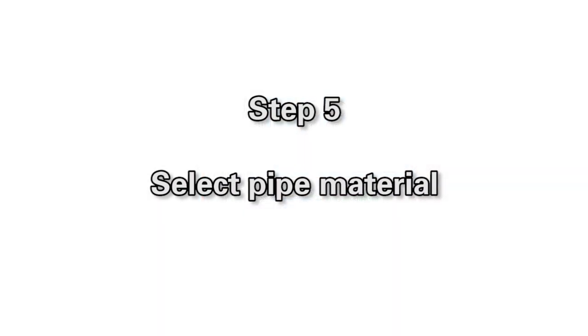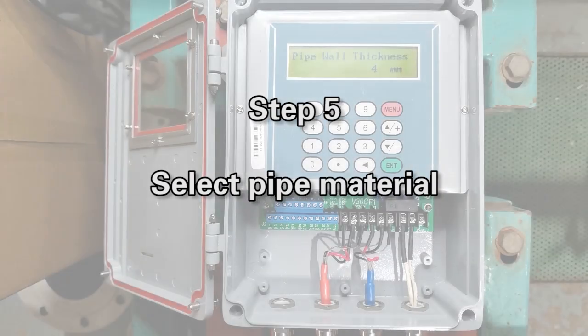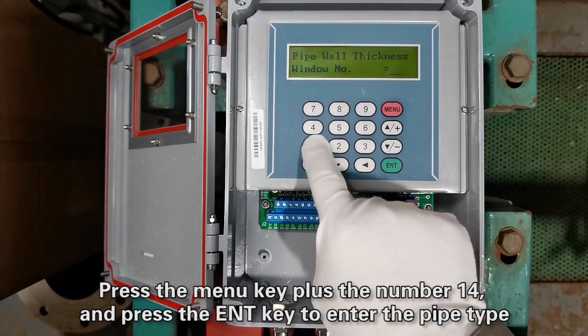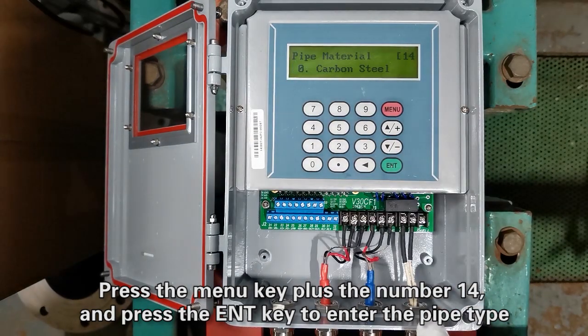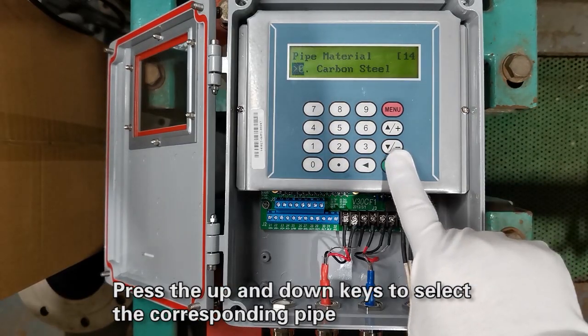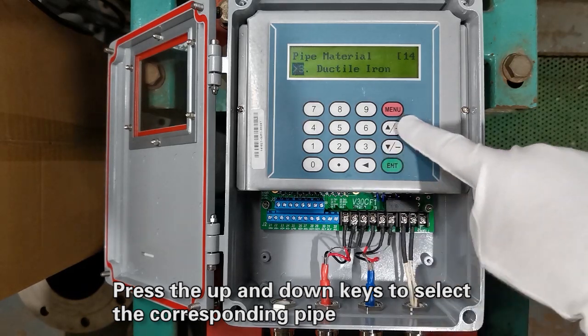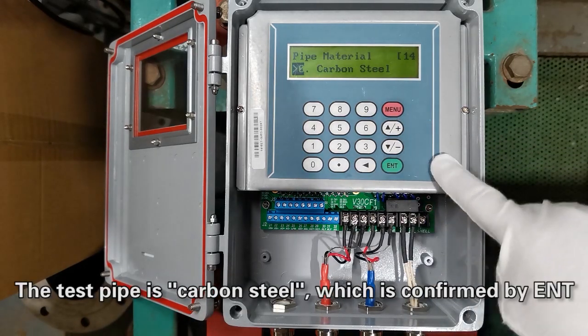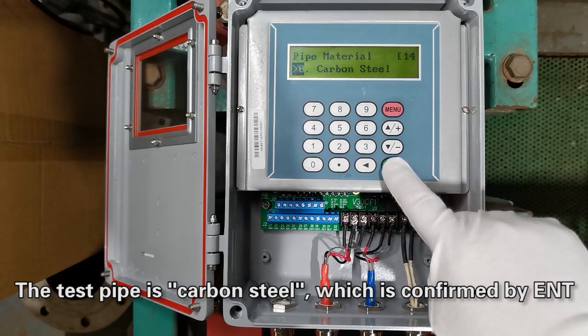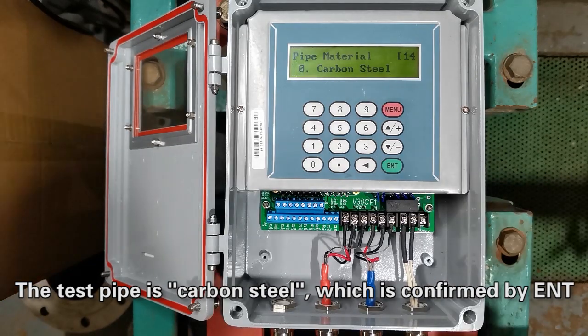Step 5. Select pipe material. Press the menu key plus the number 14 and press the Enter key to enter the pipe type. Press the up and down keys to select the corresponding pipe. The test pipe is carbon steel, which is confirmed by Enter.